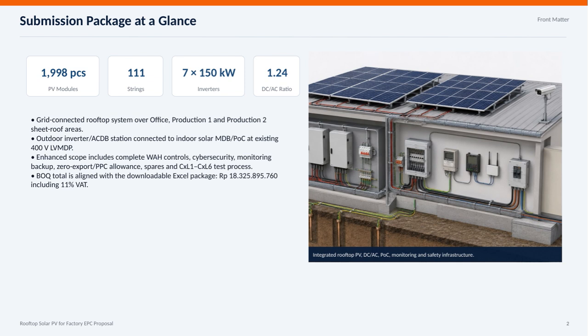The setup involves a grid-connected rooftop installation spanning the office area and 2 production sheet roof sections. An outdoor inverter and AC distribution board station will be connected to the existing indoor solar main distribution board at 400 volts. Additionally, the scope offers enhanced features such as warehouse controls, cybersecurity measures, backup monitoring, zero export limits, and a full range of testing processes from CXL1 to CXL6. The bill of quantities aligns with the detailed Excel package, with a total cost of approximately 18,325,000,000 rupiah, including VAT. This comprehensive approach ensures reliability, safety, and compliance for the solar installation.